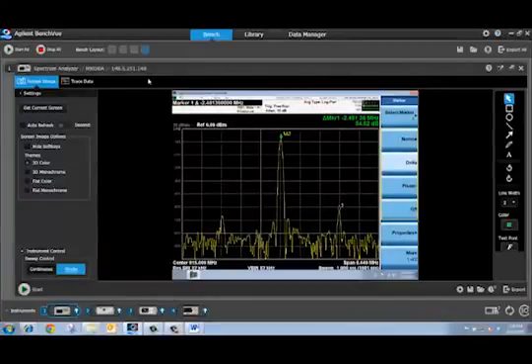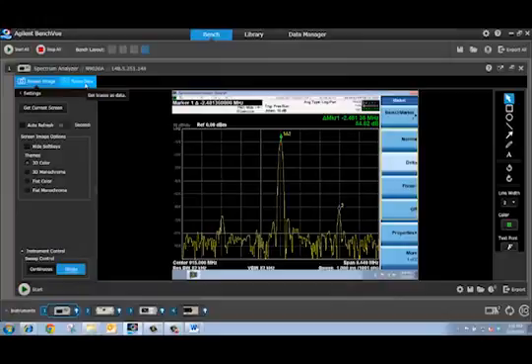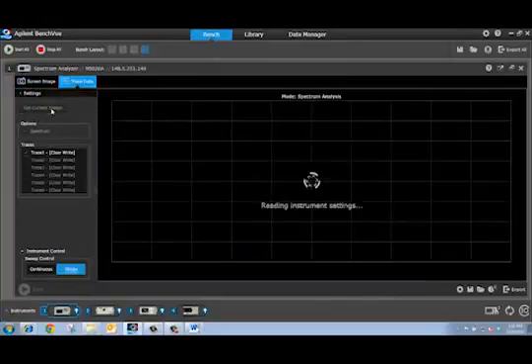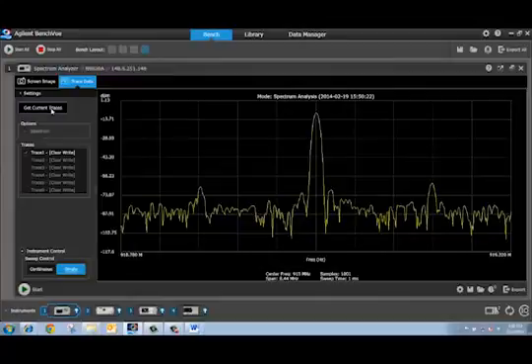I can also retrieve trace data from my spectrum or signal analyzer without any programming. Let me demonstrate. All I have to do is press get current traces and it fetches the digitized points from the signal analyzer I'm connected to.